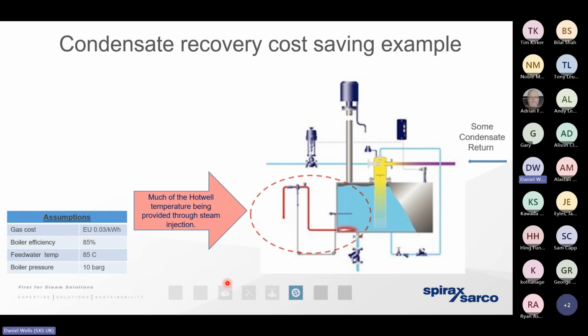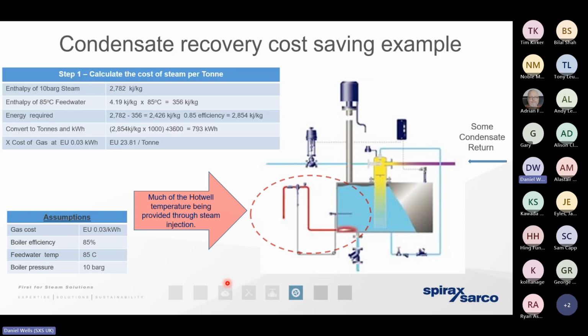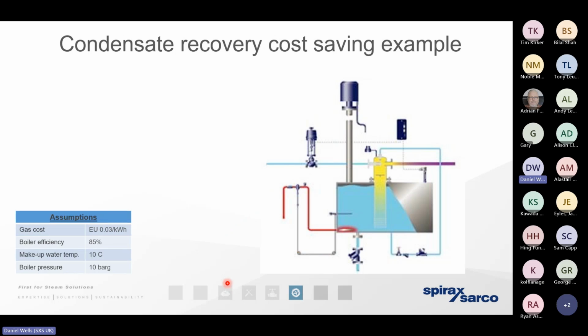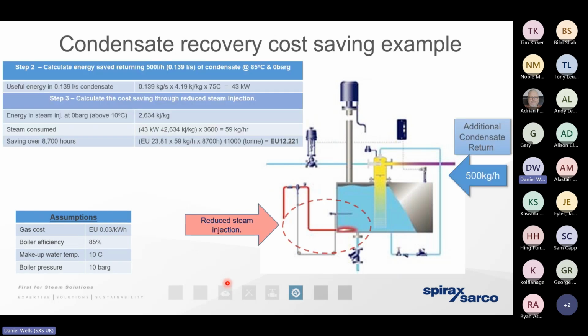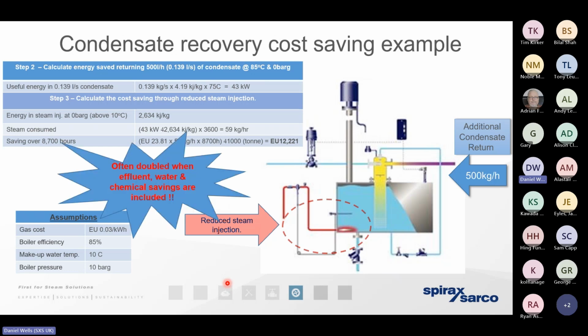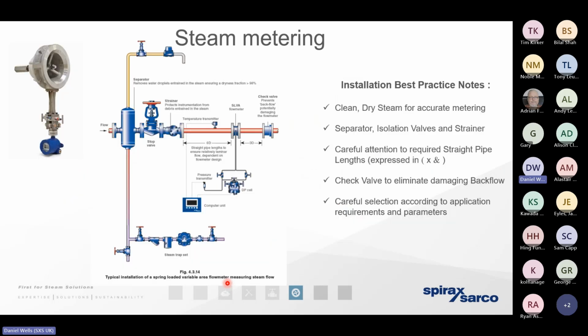So, a few calculations here. I'm not going to go through these, but it demonstrates that if we've calculated our cost of steam, and if we've calculated the mass of condensate that we can recover from condensate that's previously been going to waste or being lost to atmosphere as it goes up those vents, we can calculate what that payback is going to be. And remember, the payback's not just in terms of reduced steam or gas, it's in terms of the carbon emissions that we are no longer responsible for.